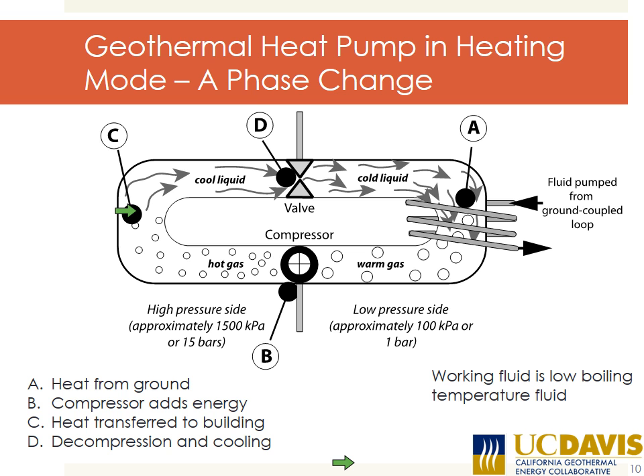At the same time, that hot gas is cooled because heat is taken out of it. It condenses, becomes a cool liquid, and goes through a decompression valve, which allows this moderate pressure cool liquid to pass through. It loses even more energy, becomes a cold liquid, flows back to the coil where it picks up heat again, and the cycle starts all over.